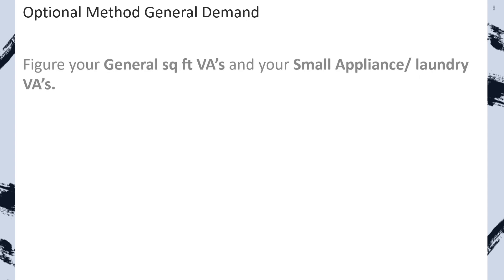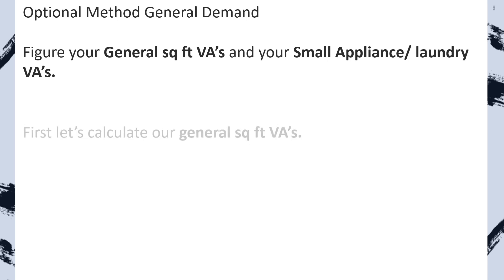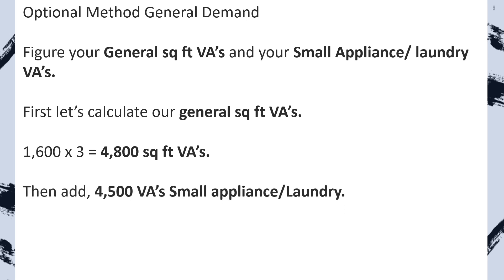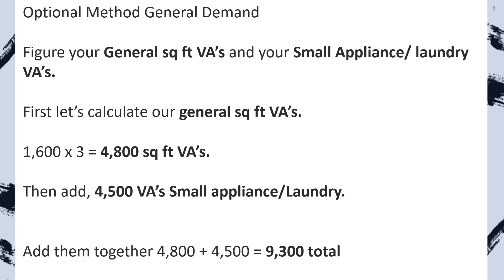Step one with any load calculation, whether standard or optional, is to get our general lighting demand. We do our square foot VAs just like before — take square footage, imagine a 1,600 square foot house, multiply by three VAs per square foot, that gives us 4,800. Now tack on our 4,500 for the two small appliance and one laundry circuits and total them all up. The only difference is we do not apply any demand factors at this point — we're going to apply a general demand factor later.